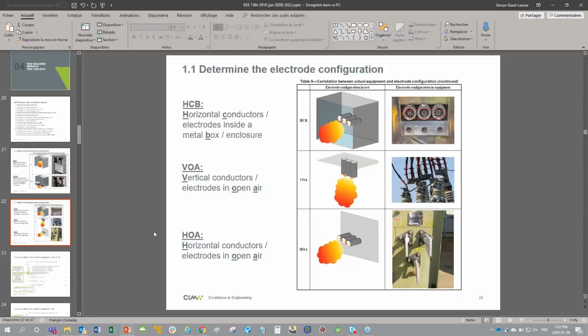And for the enclosure size, what I would recommend is going to the IEEE 1584-2018 tables. There's an appendix with some tables with some typical enclosure sizes, so these can be used. And also the EasyPower library has some equipment sizes inside, so these vary depending on the equipment type you use in your bus in EasyPower. So I would recommend using this, but just state to the client that you use typical values and the results should be interpreted with care.